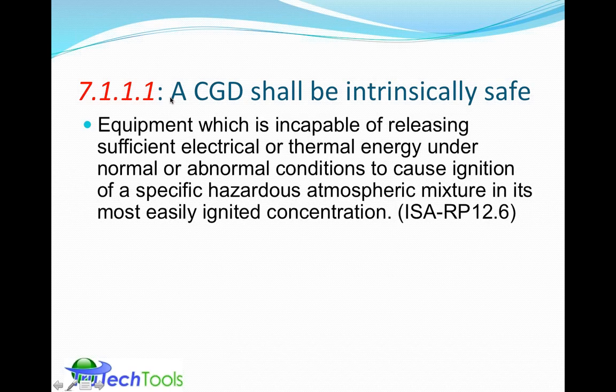Combustible gas detectors shall be intrinsically safe. Now, when that statement is made, that indicates that the equipment must be incapable of creating an explosion or ignition to an atmospheric hazard, a hazardous atmospheric vapor, in its most easily ignited concentration. So we're going to go into what that exactly means, and again, give you an idea of the science behind it.